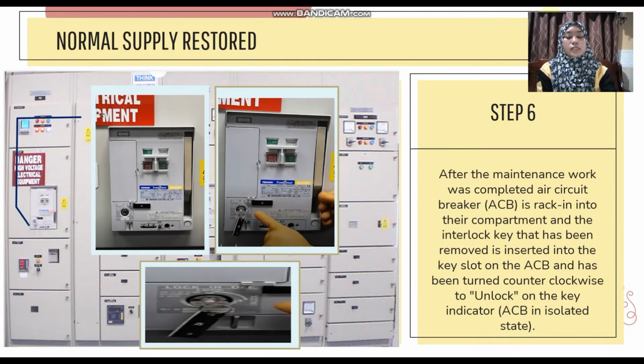Now step number 6: after we have done the maintenance of the circuit breaker at MSB1, we rack it into the compartment. After that, the key that has been removed, which is from place key number 2, which before this I said is for the air circuit breaker, we plug into the air circuit breaker at the slot of the key. After that, the key is turned counterclockwise, from here to here.